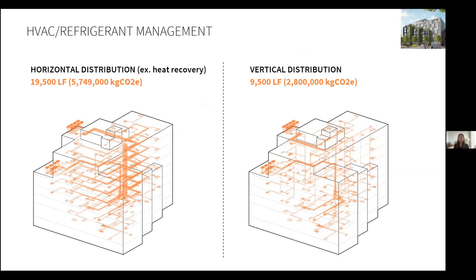Refrigerant leaks are a big concern for embodied carbon and are common at site-fitted connections, such as elbows, as the system ages. Refrigerant can have a global warming potential several thousand times more than carbon dioxide. So an example of the horizontal VRF system is a heat recovery system where two different residents on the same floor can be in heating and cooling mode at the same time.